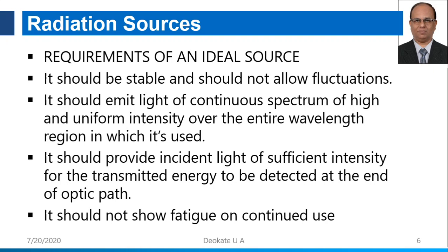We are not able to measure the absorbance directly. What we can measure is the intensity of the incident beam and the intensity of the transmitted beam. So here we can just measure the intensities, so it should provide incident light of sufficient intensity. It should not show fatigue on continuous use. Fatigue means that when heating occurs, the intensity of the radiation might change. This should not happen. That is called fatigue.